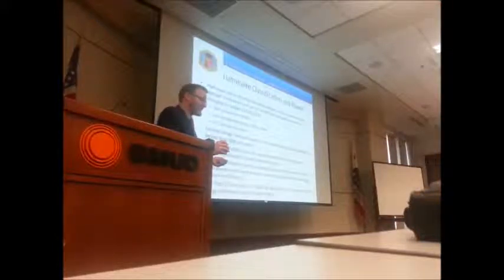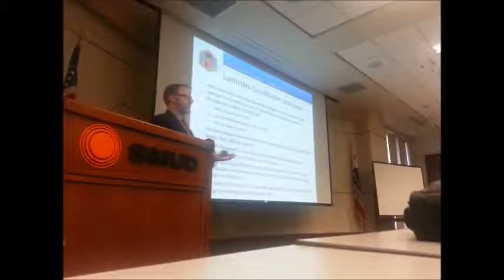So on this one, we're going to basically trust people. If you've got a ballast that can drive up to 42 watts, but you're only using 26, we're going to say it's a 26-watt luminaire. Because in real life, in a commercial building, if you've got 26-watt lamps in it, the facilities person is probably going to replace them with 26-watt lamps. They might bump them up or down a little, but they're not going to want to make one luminaire brighter than all the others. So we think that's going to work fine, and we don't want to make people's lights too high.